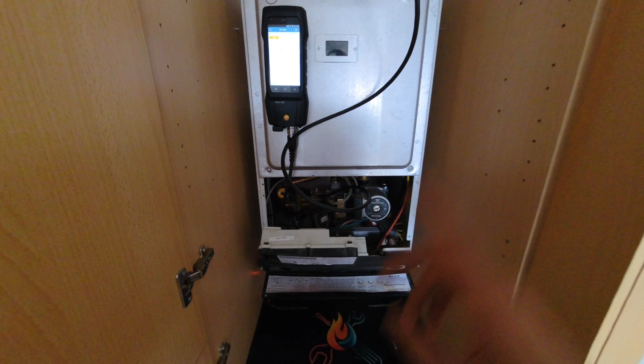That puts the diverter valve into hot water position. Then open up a hot tap, put it into service mode, and it will divert all of the heat through the plate and then out to the hot tap. So it just makes it a little bit easier when you're doing your gas rating and your flue gas analyzer checks, to make sure that the boiler stays within its temperature limits and doesn't get too hot too quickly.